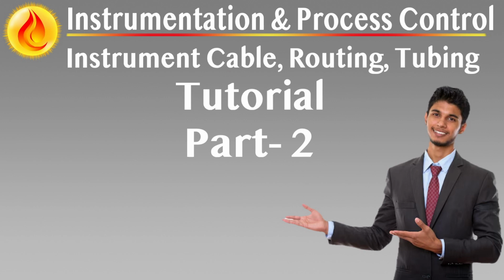For screened field cables running between junction boxes and MDFs, the screen must be earthed only at the MDF. At the field end, the screen should be insulated, left unconnected, and kept the same length as the signal wires to enable future integrity checks or continuity testing. Cables routed directly from the field instrument to the receiving equipment, bypassing junction boxes and MDFs, must have their screens earthed only at the receiving end.